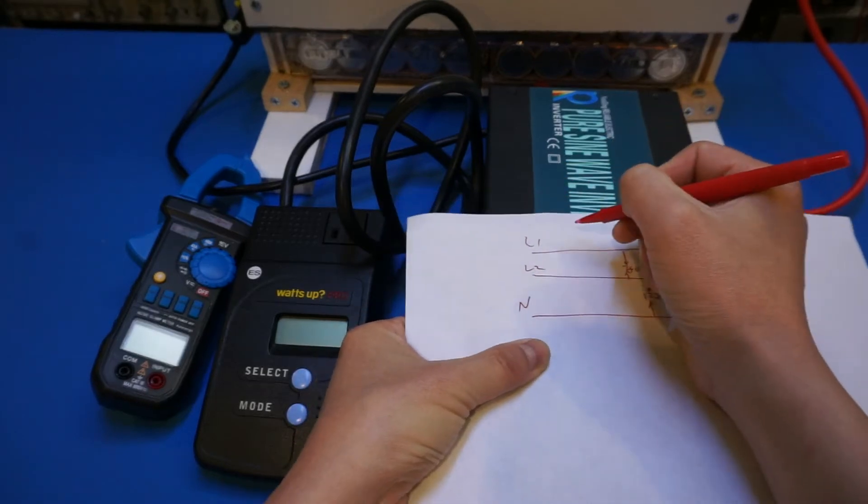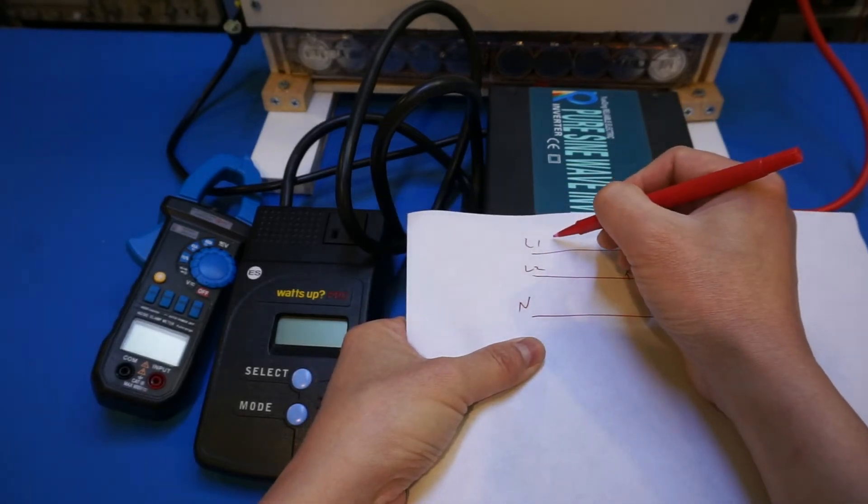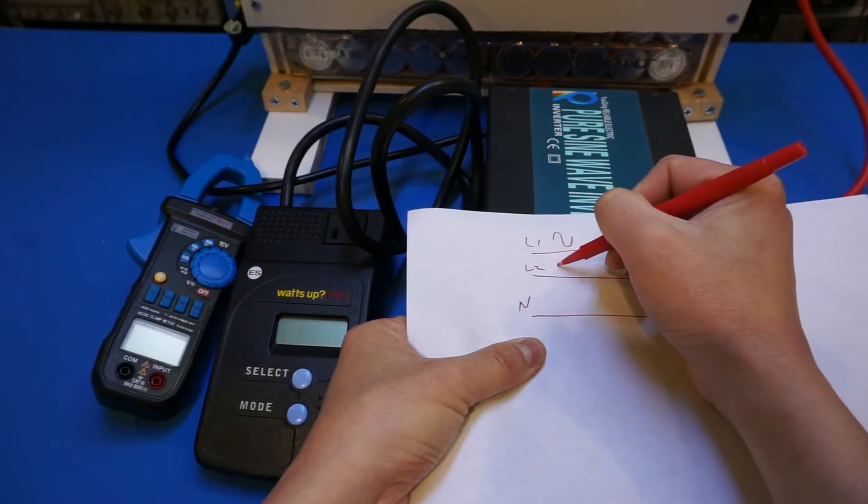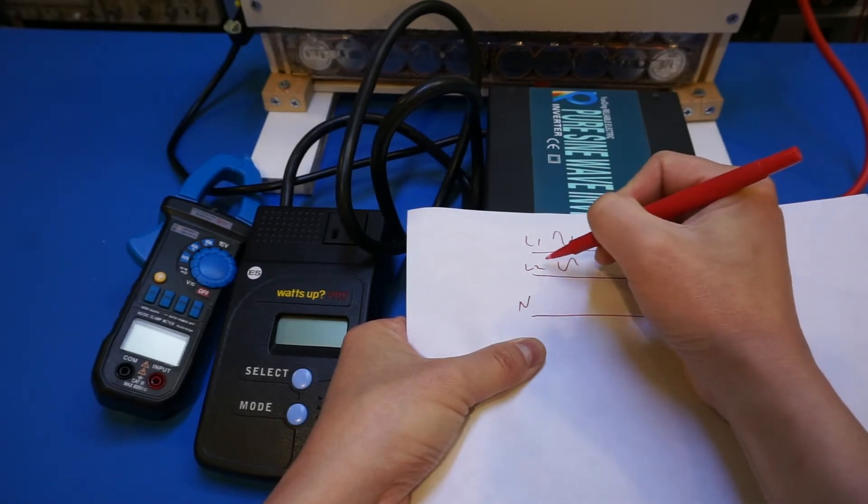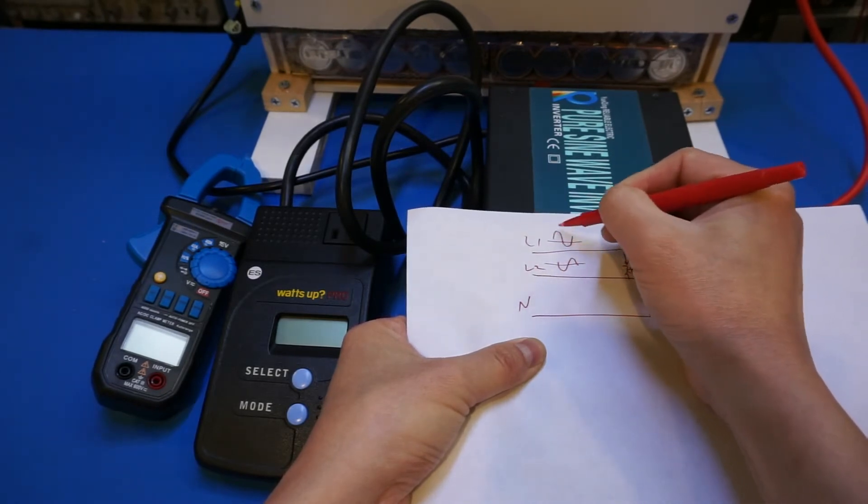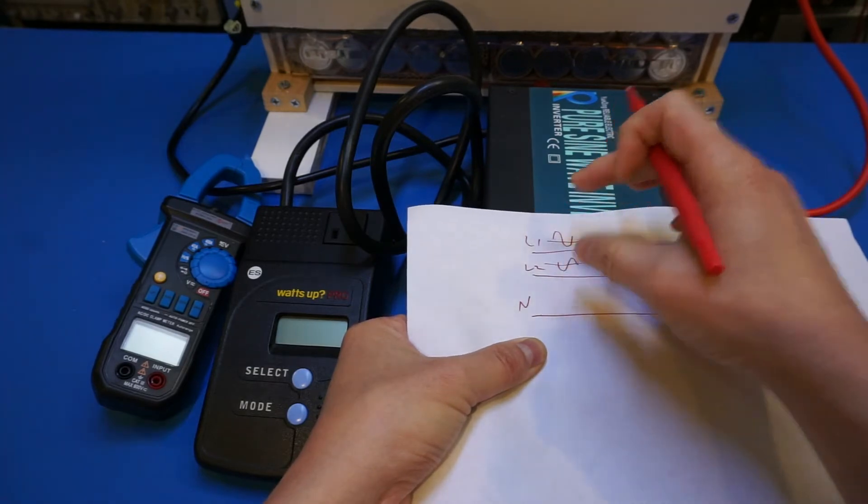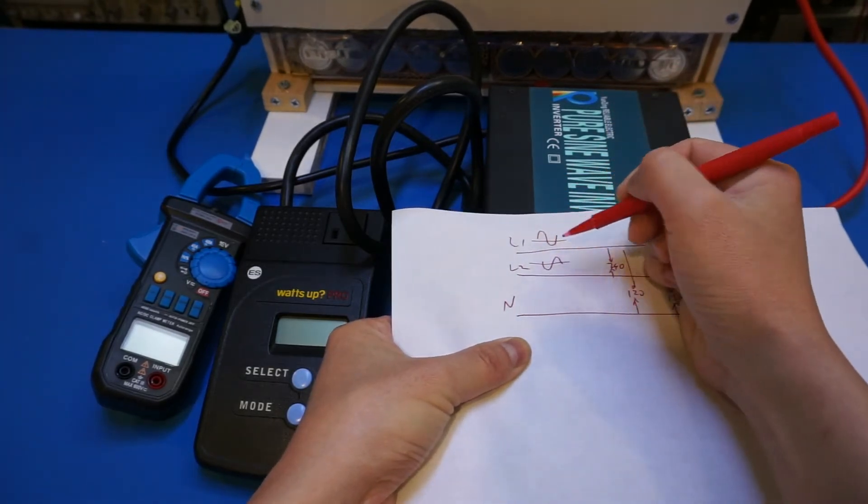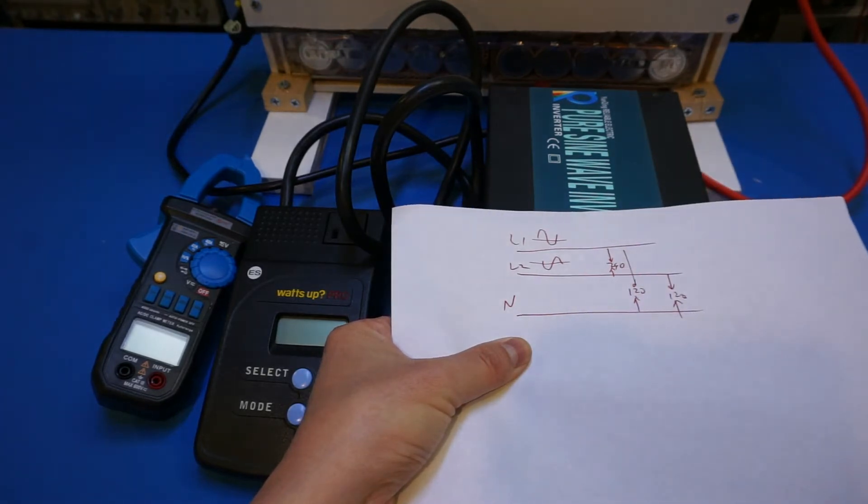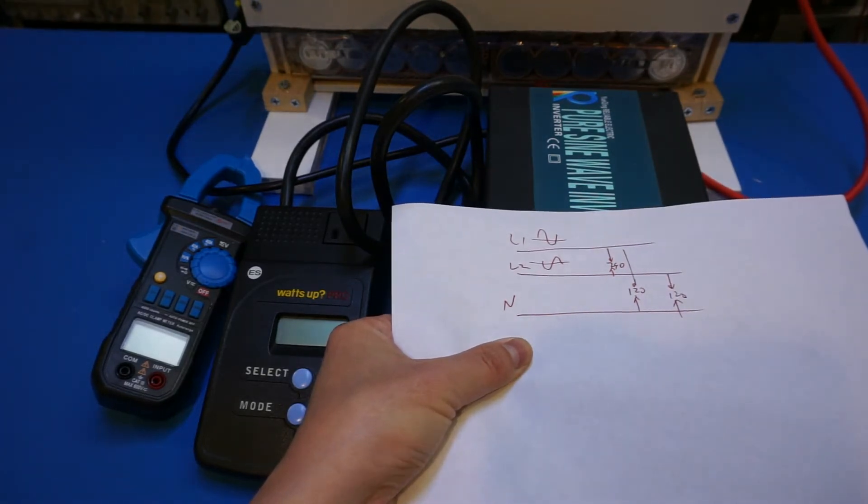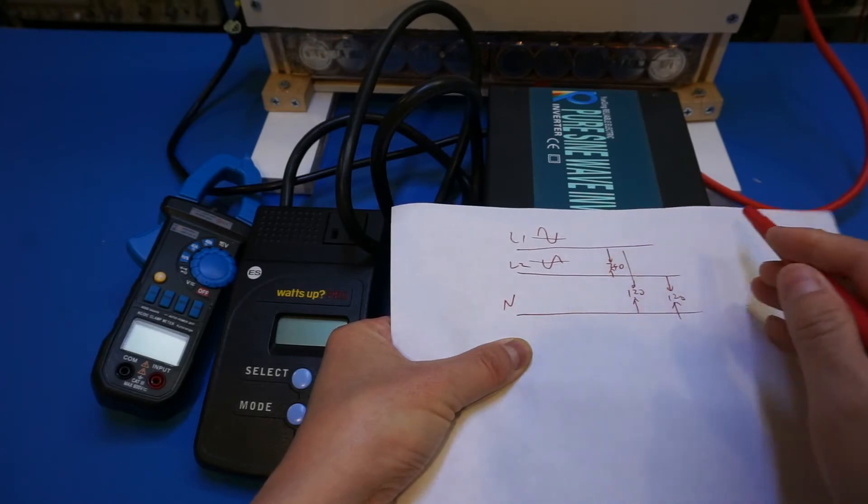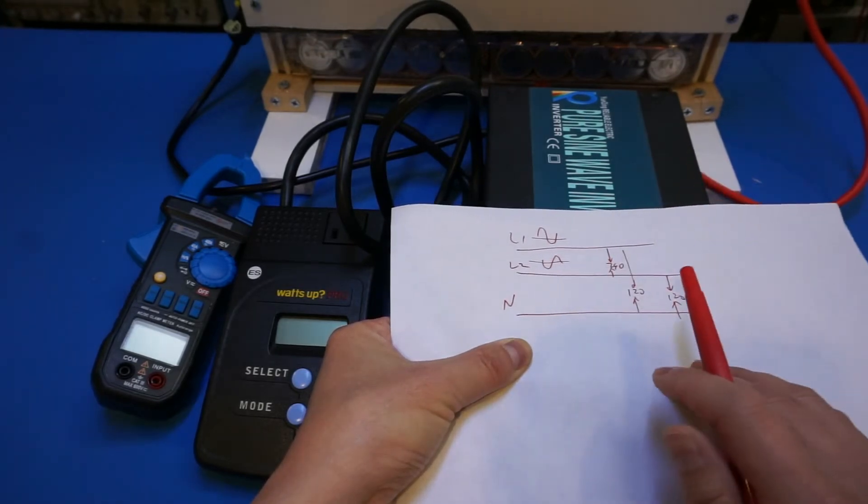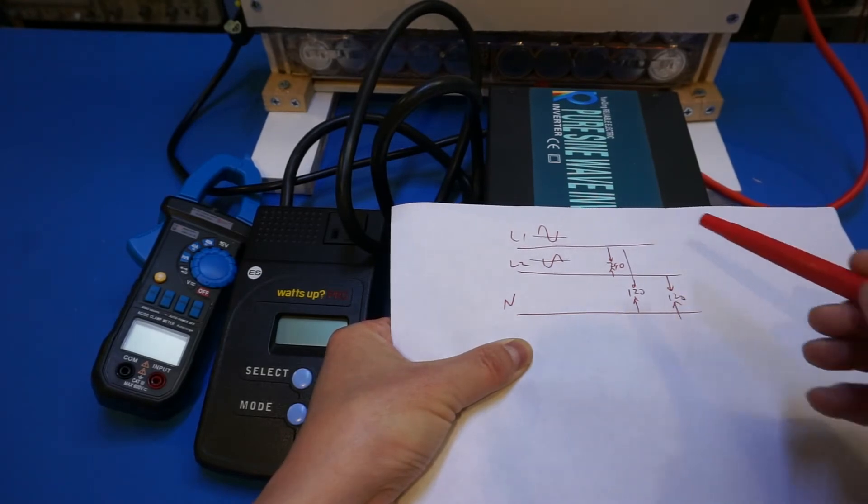The reason is because the waveforms coming in are exactly 180 degrees out of phase. So they're opposing each other. And at any given moment, the difference between those is a sum of that waveform. So it's 240 instead of 120. So this is how you get 240 in your house for clothes dryers, water heaters, and ranges.